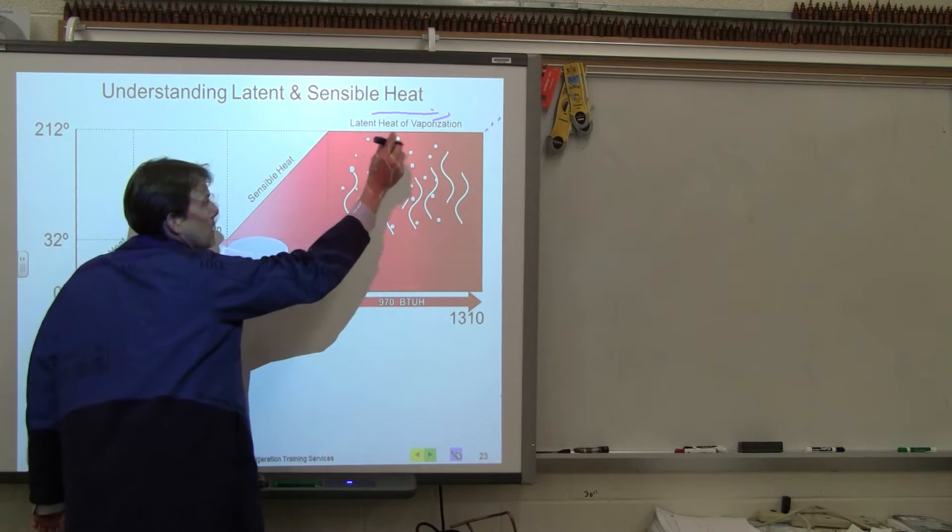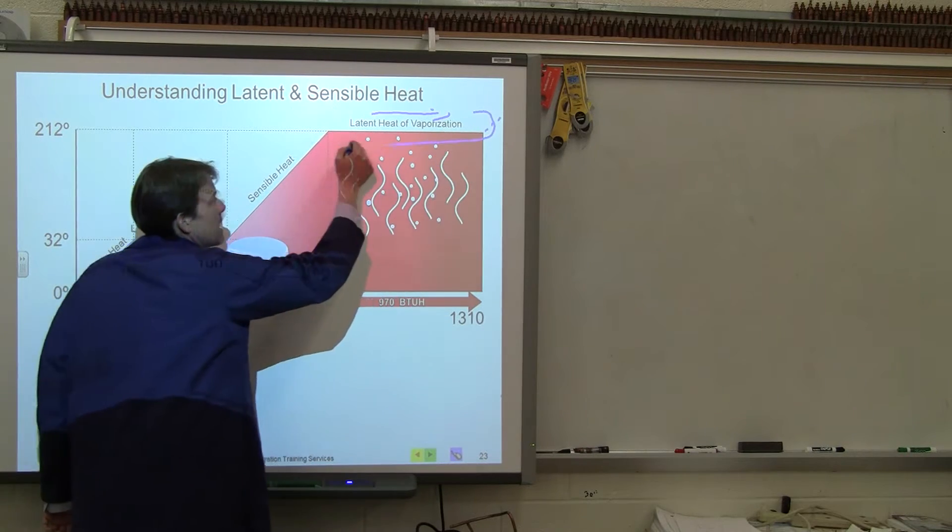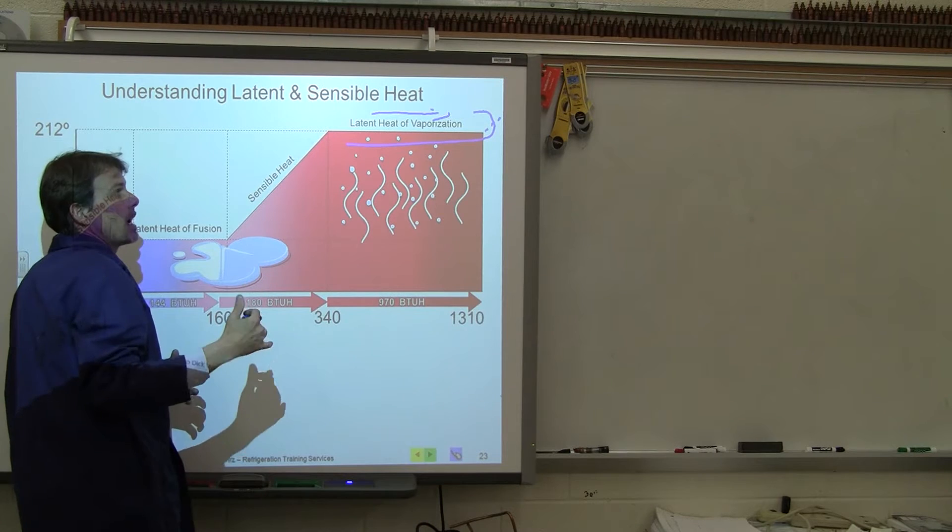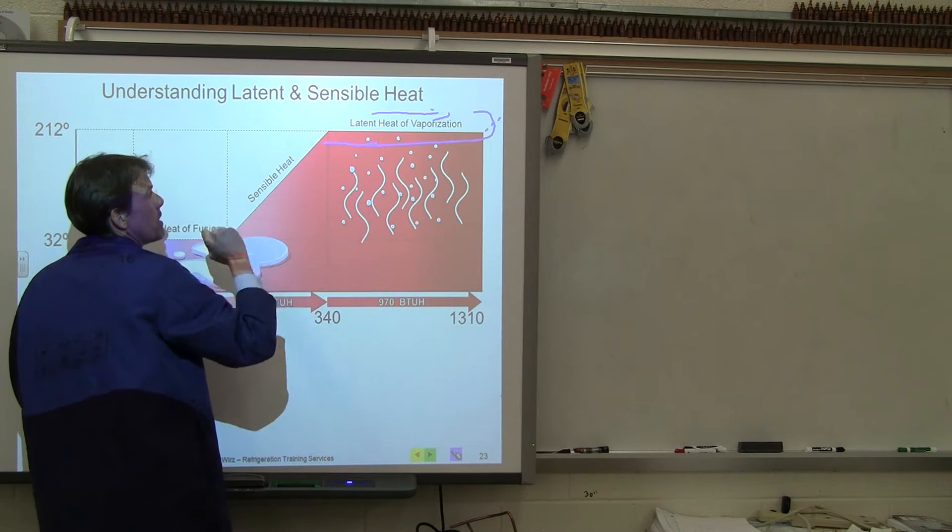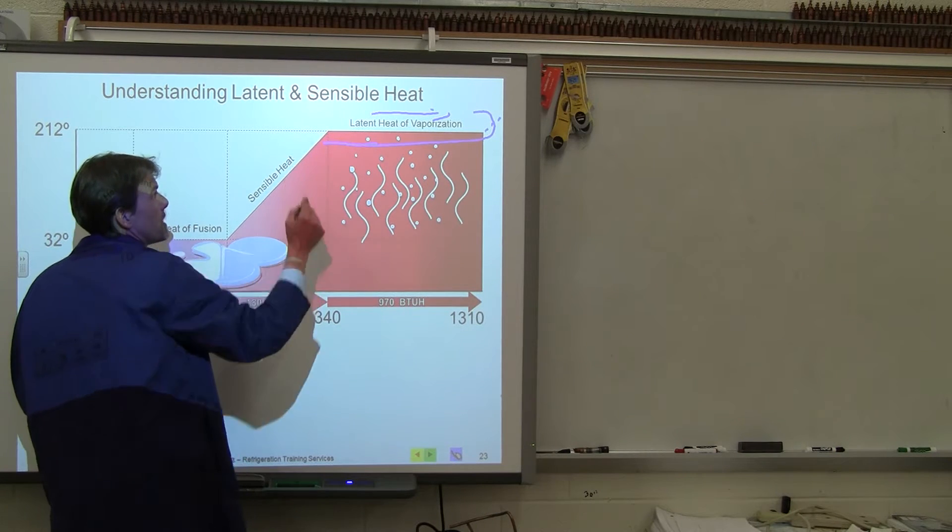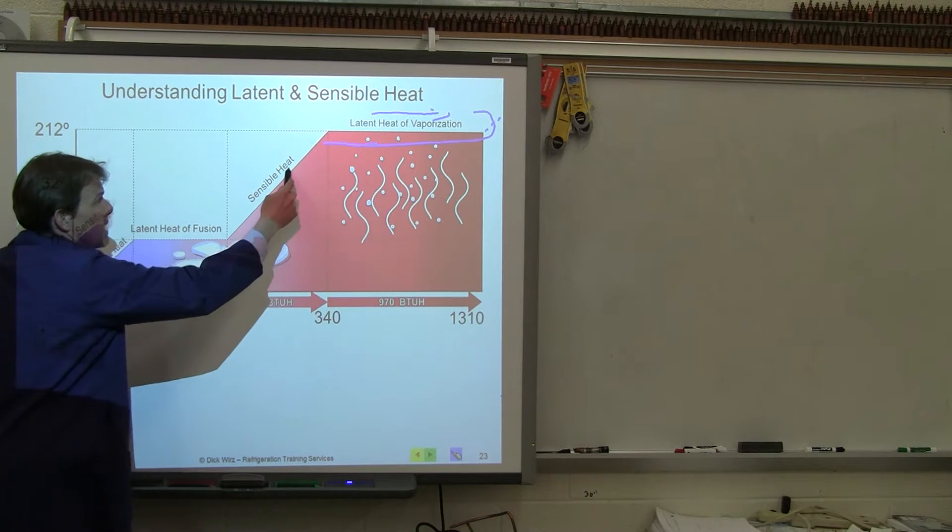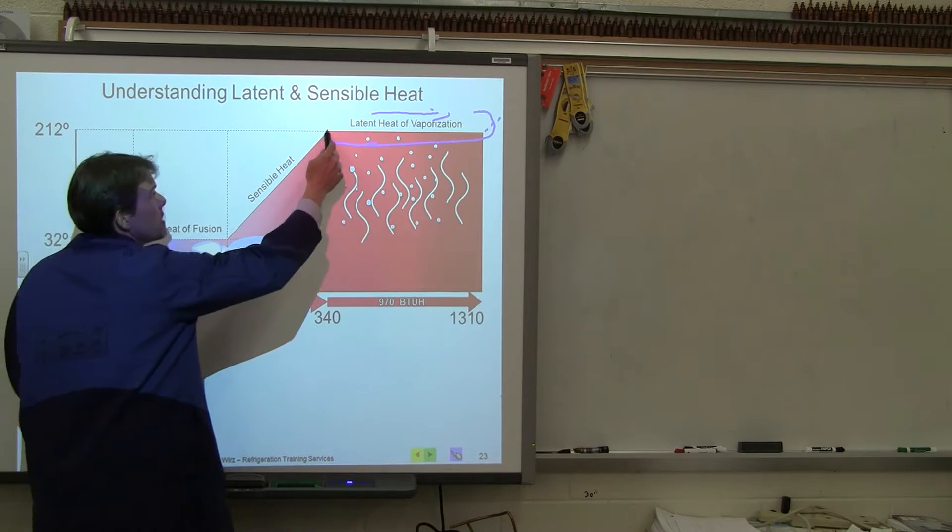Then we come back down into here for the condensing out in the outside unit, for the condenser when we're rejecting our heat. The subcooling comes over here when we get a few degrees below the saturation temperature. We can get really any temperature below, and that would be subcooling.